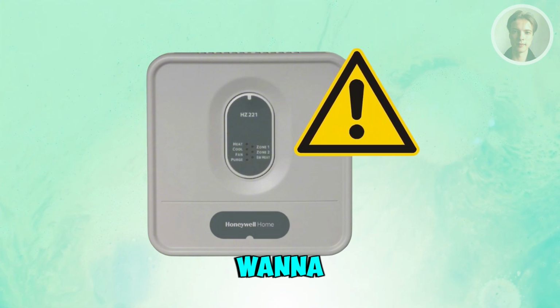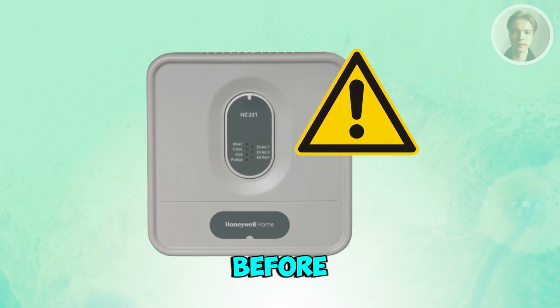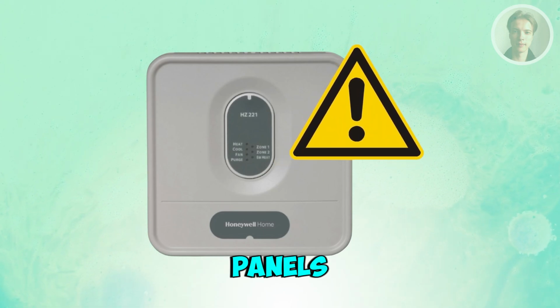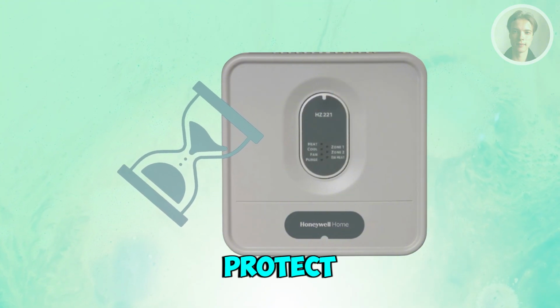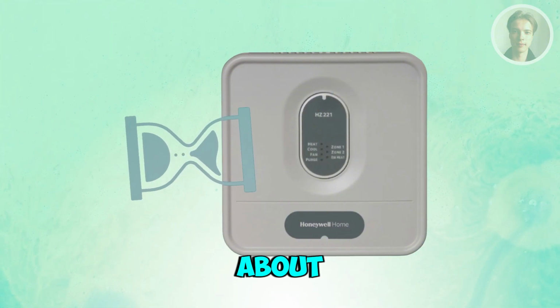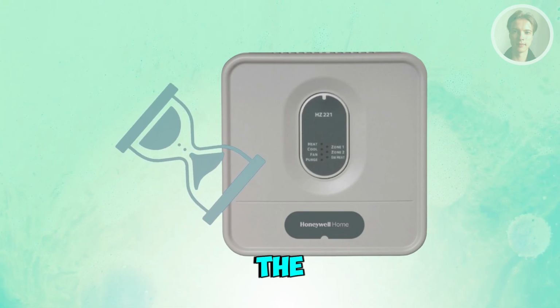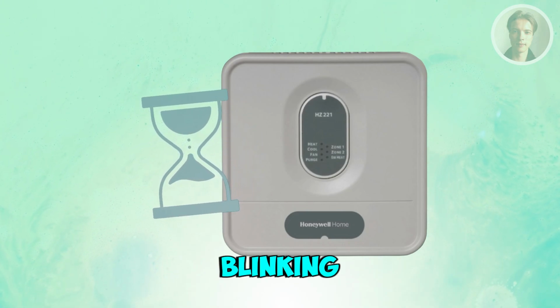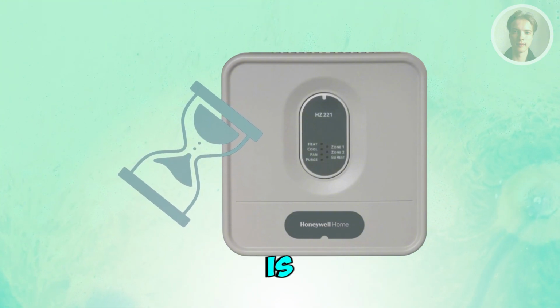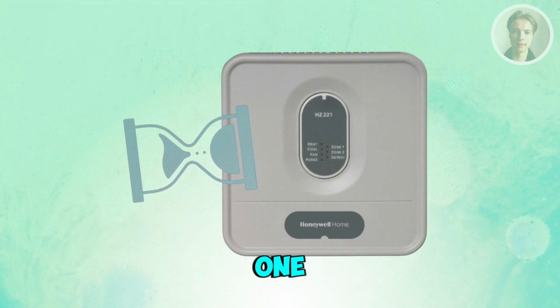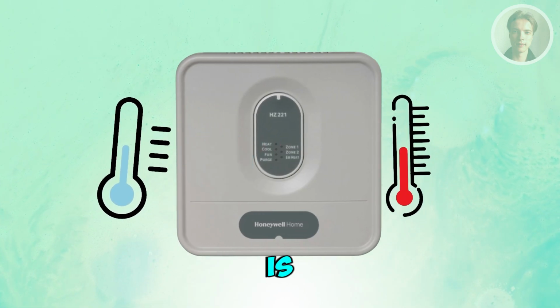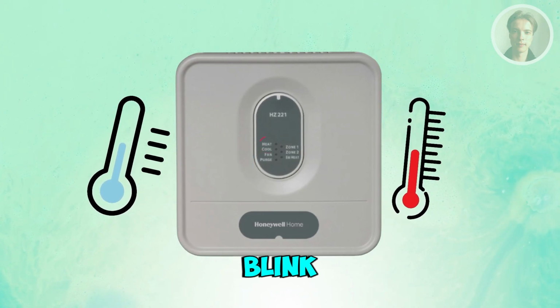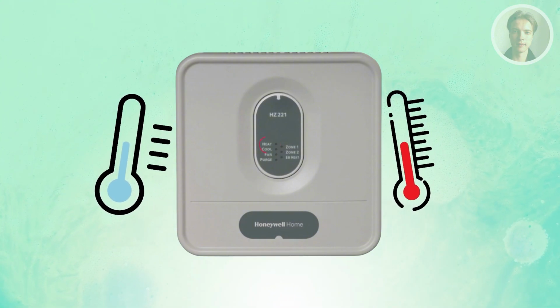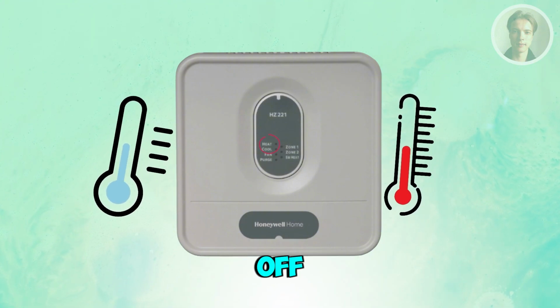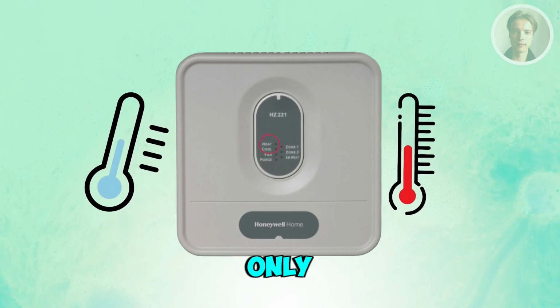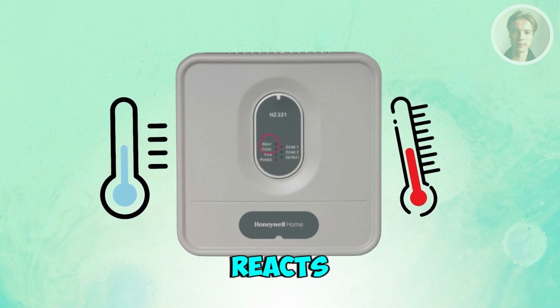Now, next thing you want to do is give the system a few minutes before touching anything here. Now, TrueZone panels intentionally delay operation to protect the compressor or furnace. Now, wait for about 3 to 5 minutes here and watch the LEDs. Now, if they stabilize, the blinking was normal behavior, or in this case, is alright. Now, if one of the zones is calling for cooling while the other is calling for heating, well, the panel can blink as it tries to resolve the conflict. Now, you want to set all the thermostats to off. Wait a minute, then turn on only one zone and see how the panel reacts.